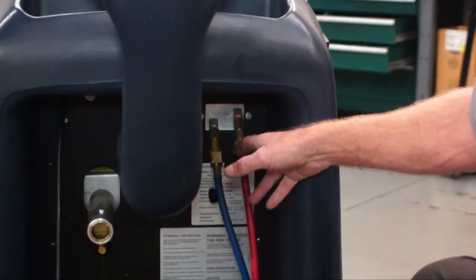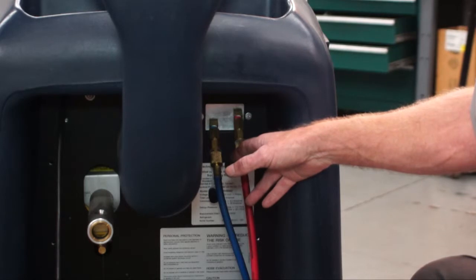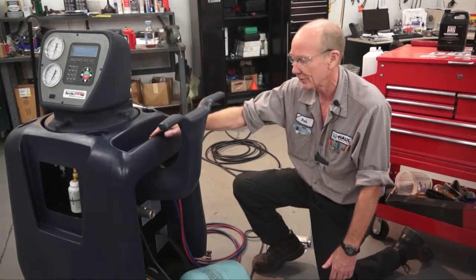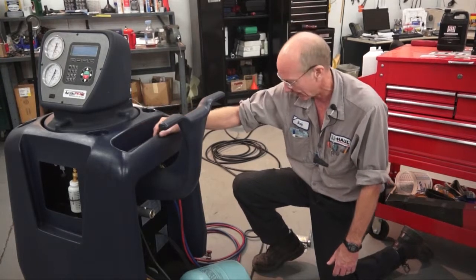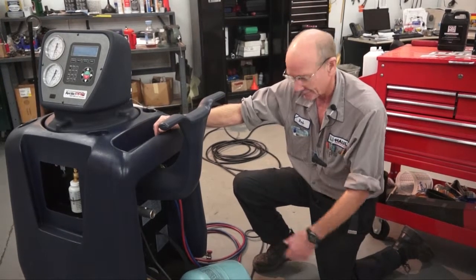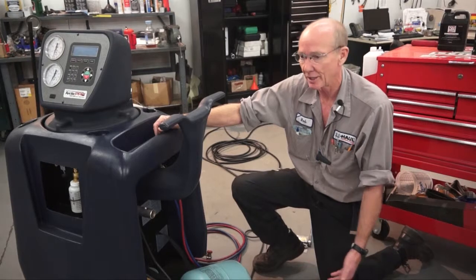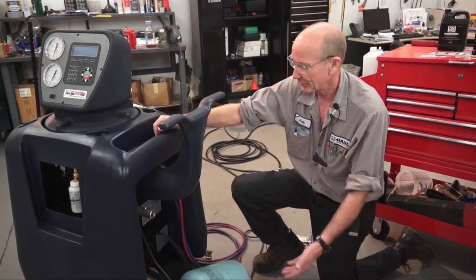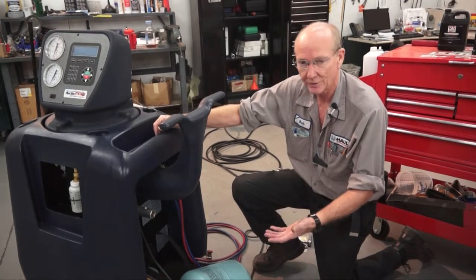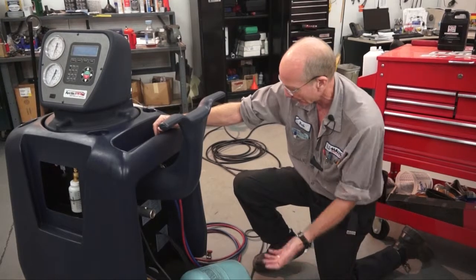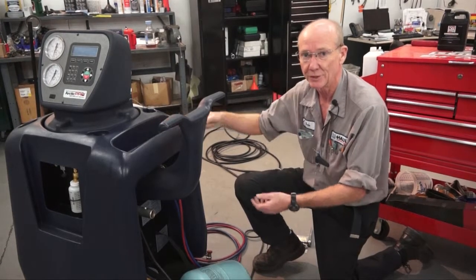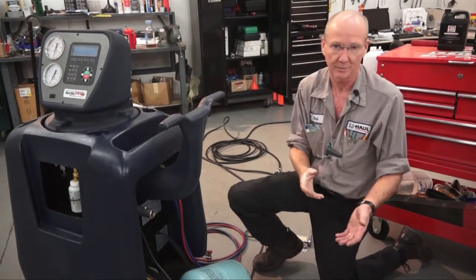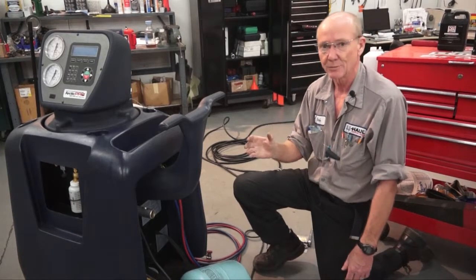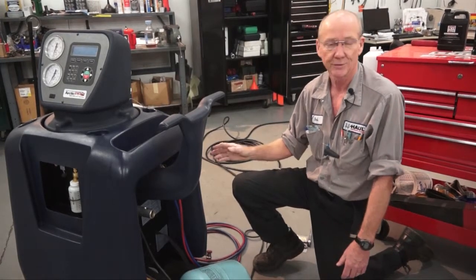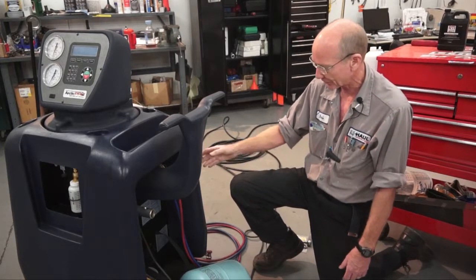You also should replace these filters, whether you're replacing the vacuum pump oil or not, if you have a contaminated system, just like I showed you with this orifice tube. The vacuum pump oil could have been changed just recently, but if you have a contaminated system with a lot of debris in it, you're pulling the refrigerant oil in, and you're going to plug up those filters, and then you're going to push that debris right back into the system again. So if you have a system with a lot of debris, you must replace those inline filters. It's a good practice, especially on the high side.